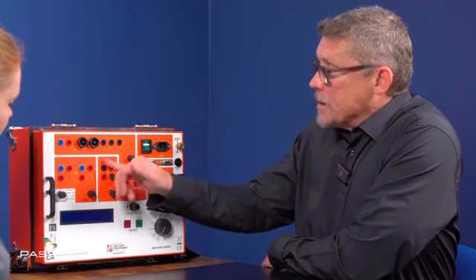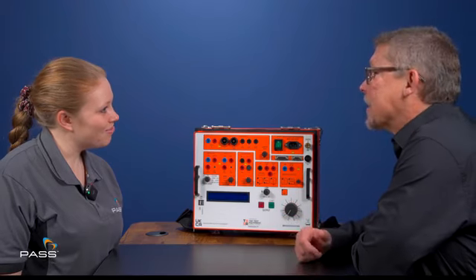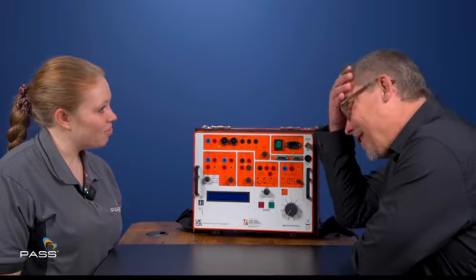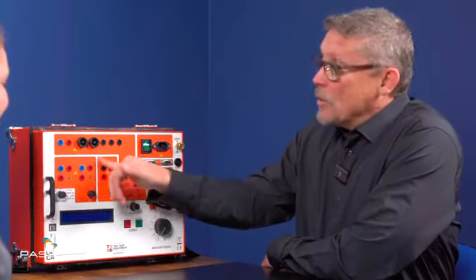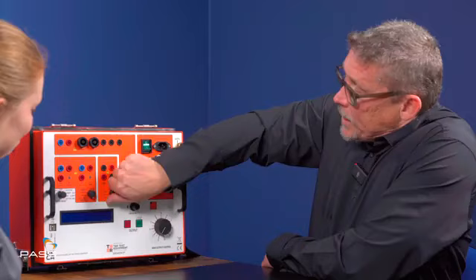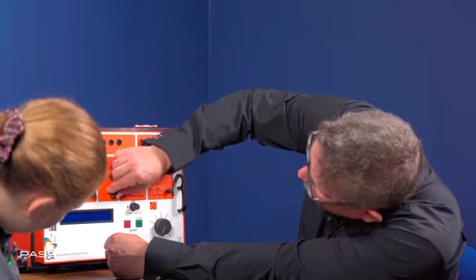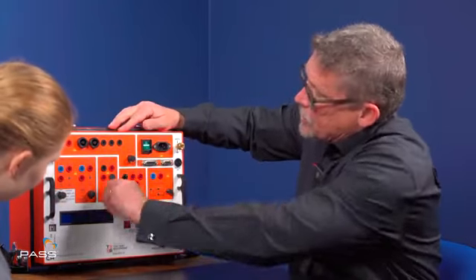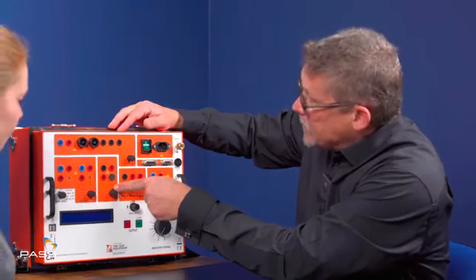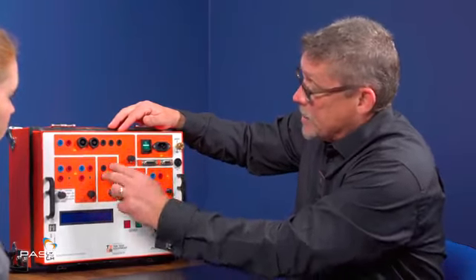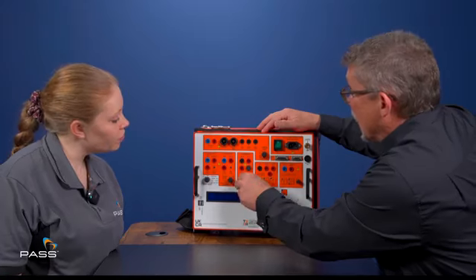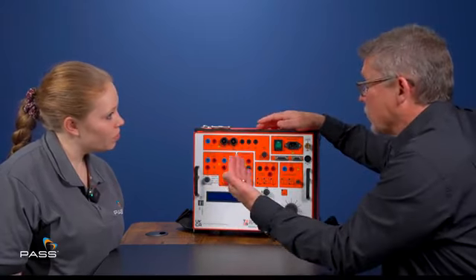Now, the reason we have the auxiliary metering is multi reasons. Invariably, when somebody goes to commission a sub, they're going to have a multimeter. But how many times have I been to the substation, opened up my thing and thought, the multimeter's on the desk? We've got a multimeter built in effectively. And what we can do is we can use it to measure. If we start at the top here, we've got DC. DC multimeter is predominantly for setting up my battery. Okay. AC has a great number of reasons we'd have it on there.